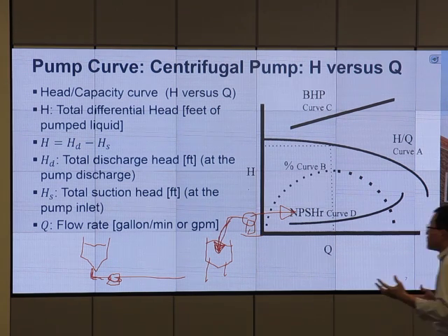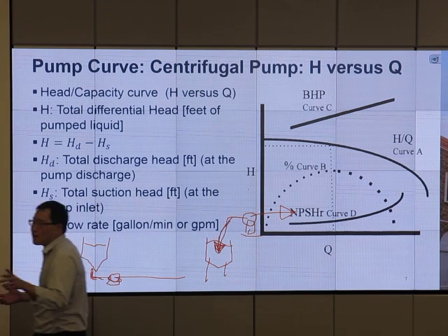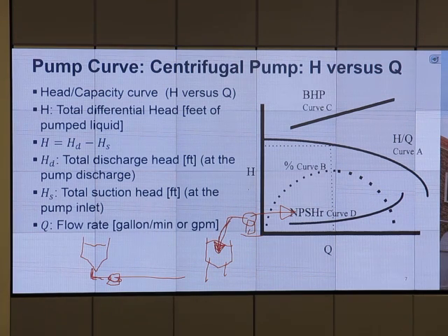You don't want to do this because initially your pump will have air in it, right? When you turn it on, have you ever turned on a fan? You turn on the fan, it just spins. Nothing happens, really. If you spin it for a while, it will wear and you break the pump. You don't want to run the pump dry. It is even worse for a PD pump, positive displacement, because you have metal contact. For a vane pump, you need some lubrication. You don't want to run dry.